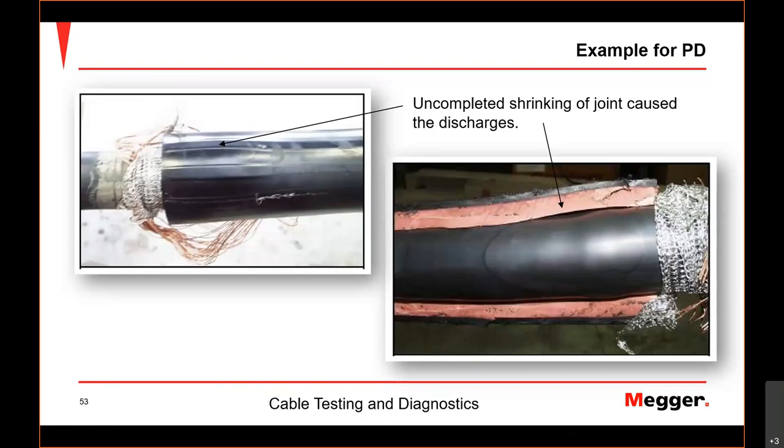And that's the point. A partial discharge is an excess of electric field, a concentration of electric field in a small spot. The isolation medium doesn't hold it anymore, and so you get a very small flashover, not the whole voltage, but just a very small flashover. We're talking about picocoulomb here, maybe one or 10 nanocoulomb in that range, but having that continuously over months, then here you see that there was something burning, sizzling in your cable, and it was detected on time.